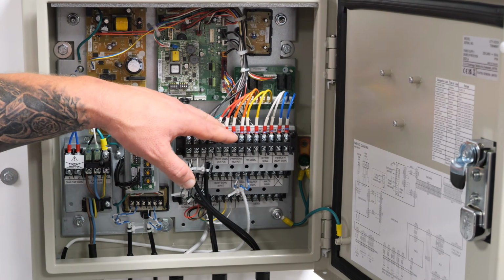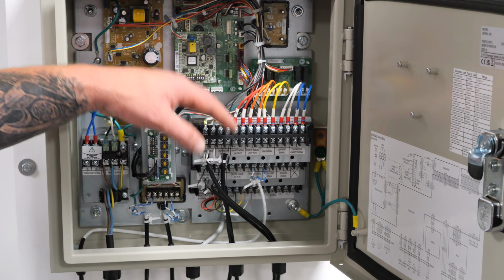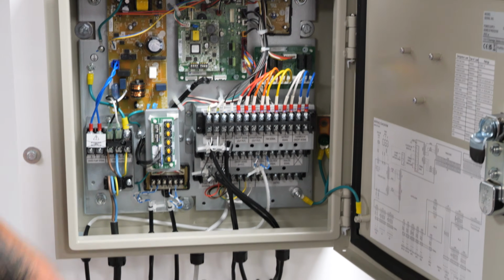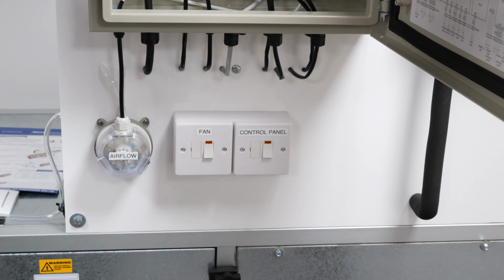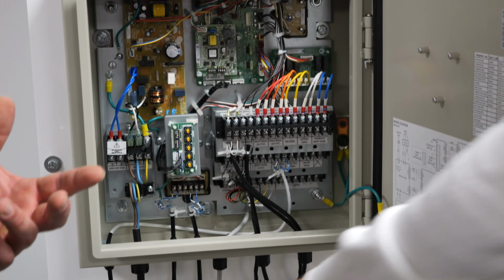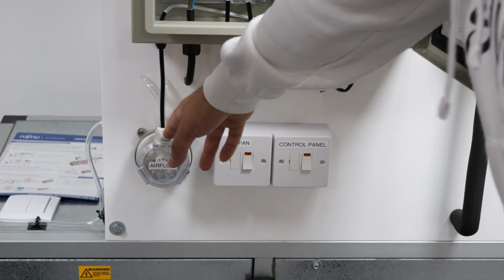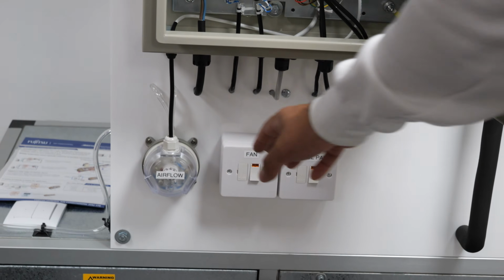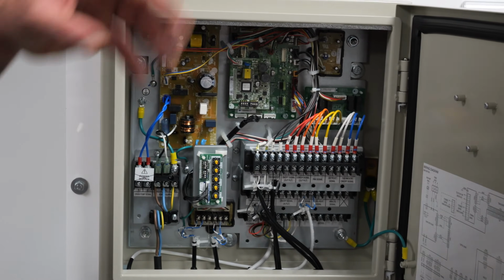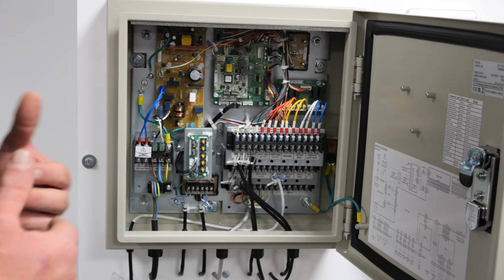You can then put in, obviously, if the fan shuts off, a flow switch, so it would shut the unit off, make or break. So it doesn't keep running and then freeze up. This kind of stuff, this is usually from a BMS supplier. Is that the case? Can be, or you can just put one on the side of the unit. So if it's picking up stopping airflow or filters blocked.